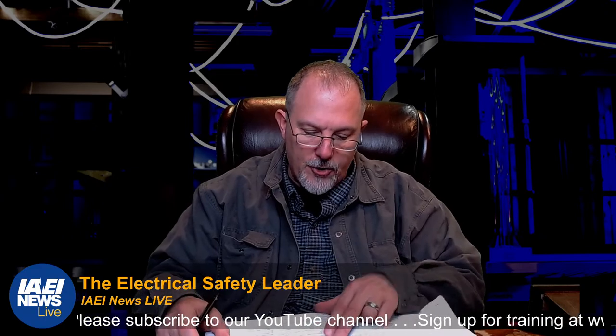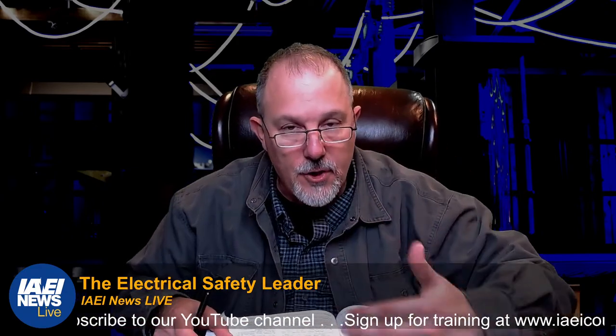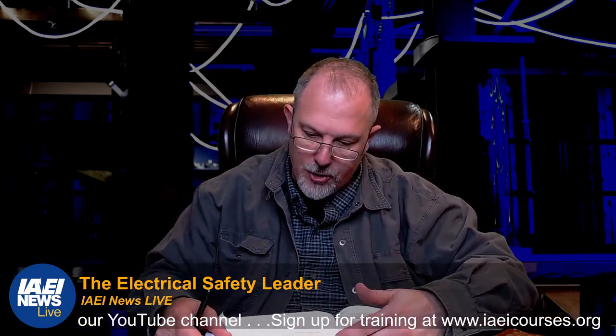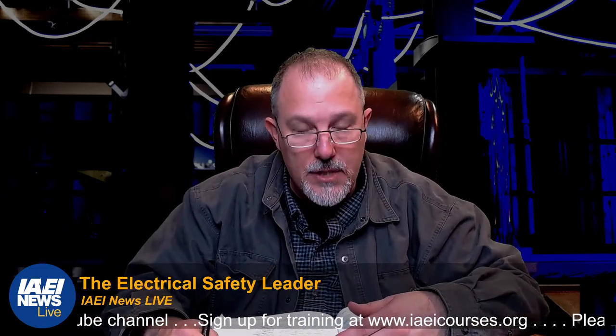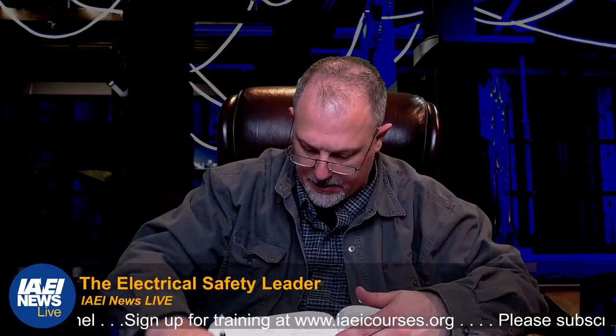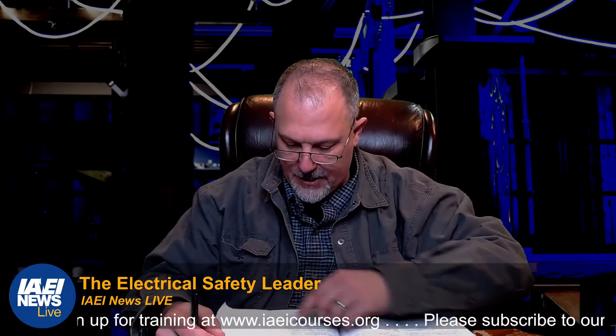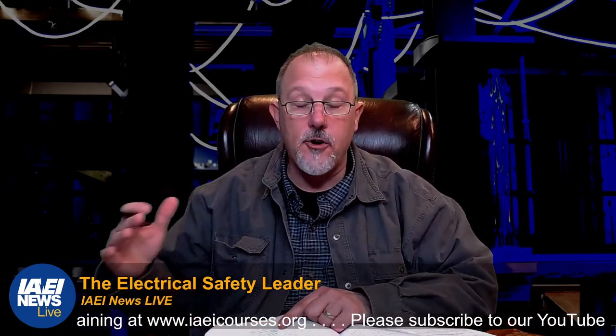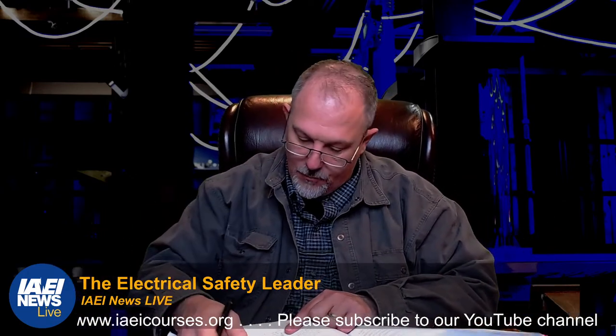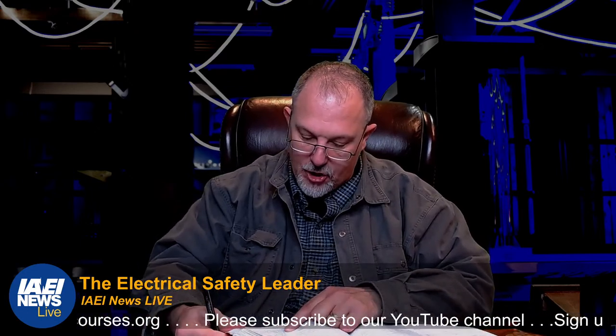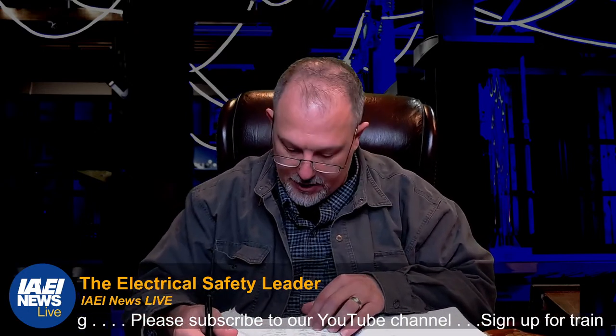Part four are your circuit requirements. This is where you're going to have your circuit sizing and you should have overcurrent protection. 706.31 tells you how to protect the conductors, how to size the conductors. They have charge control - provision shall be provided to control the charging process of the energy storage system.